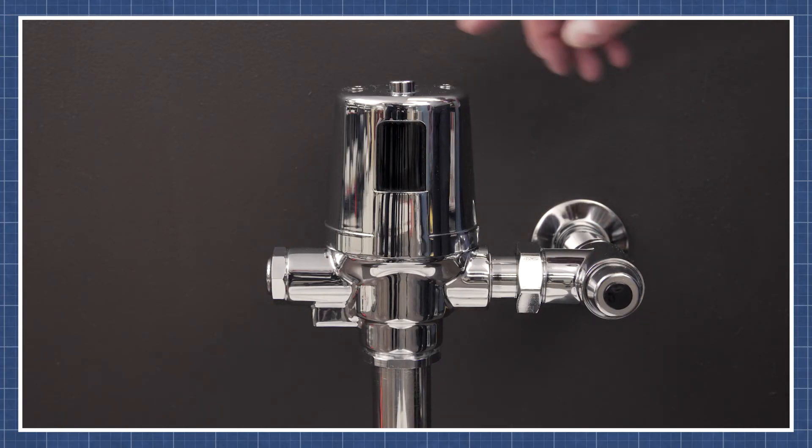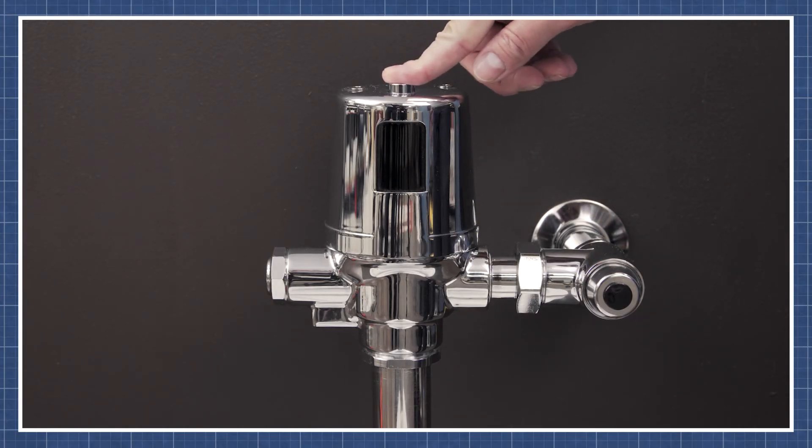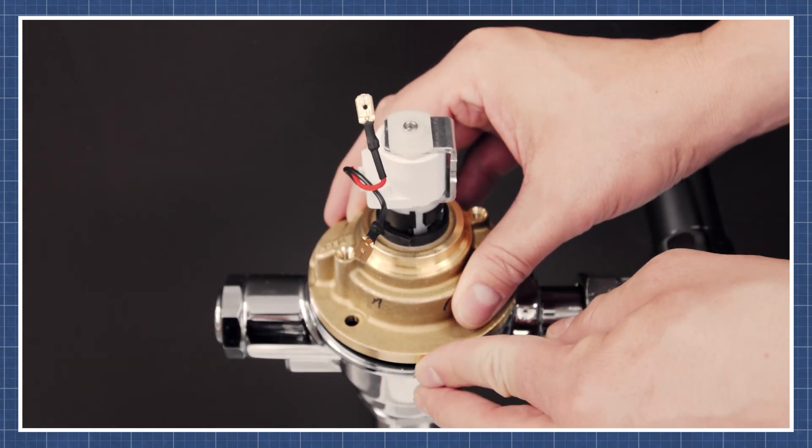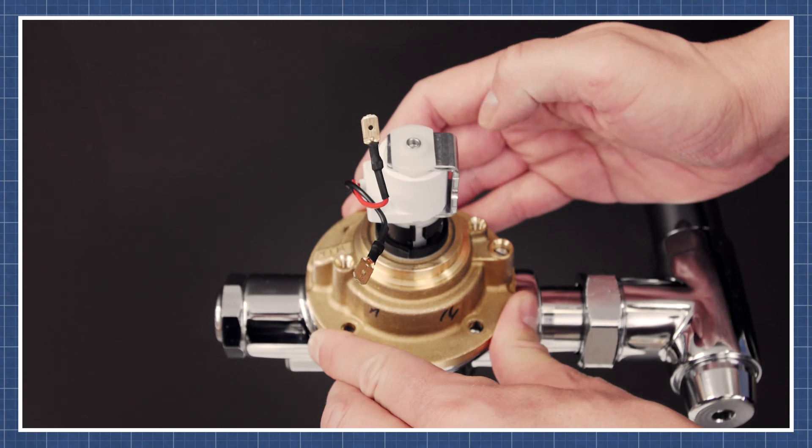When the unit has power and the lights are showing, but the valve doesn't flush, check to see if the solenoid makes a clicking sound. If there is no sound, then replace the cast cap solenoid assembly. You can watch this in the video linked below.